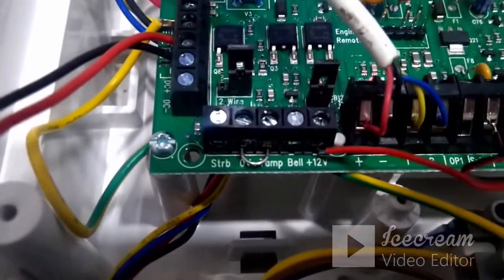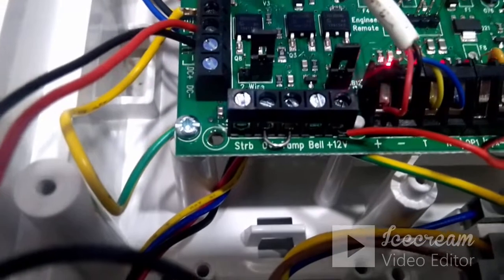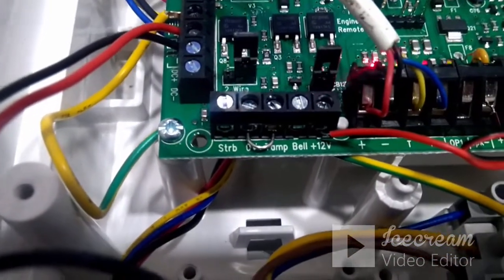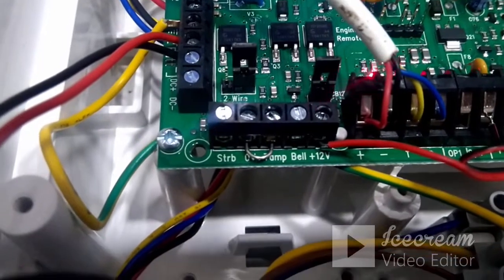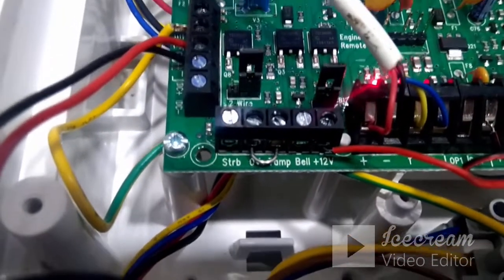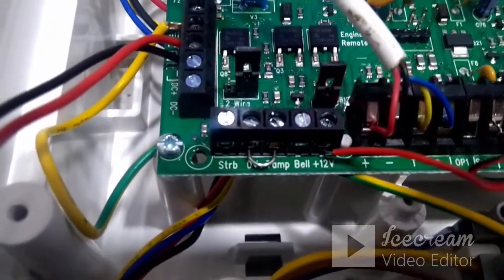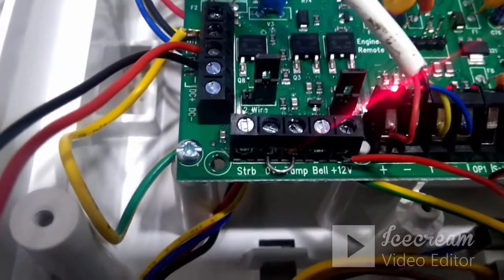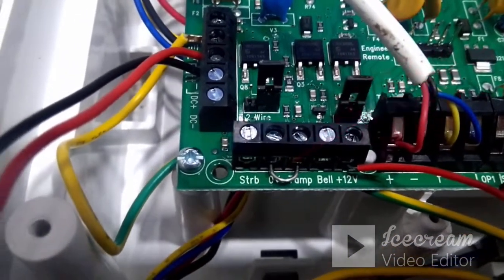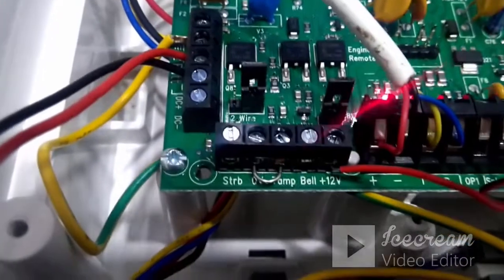If the sounder is not a Texecom sounder but some other make, those sounders may have only two terminals: plus 12V and ground. In that case, the plus 12V connects to plus 12V on the panel board, and the ground terminal connects to the bell terminal on the panel. If you have more than one sounder, the second sounder connects between plus 12V and the strobe — positive to plus 12V, ground to strobe. So two sounders can be connected at a time on this panel.